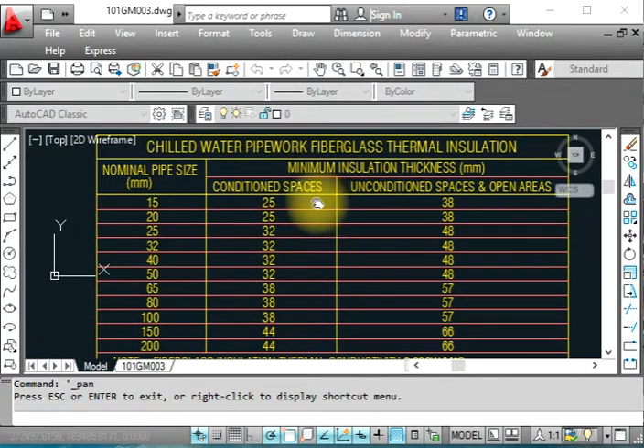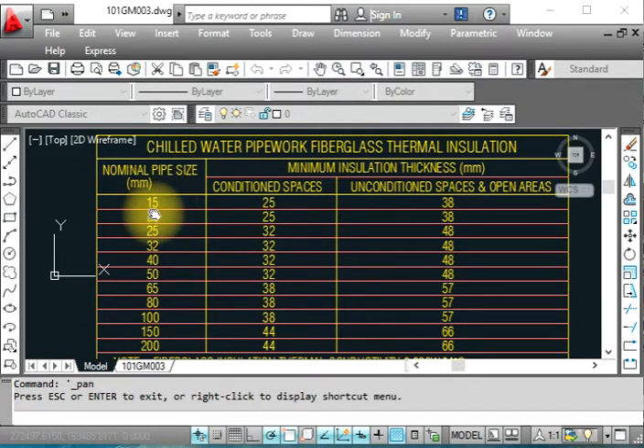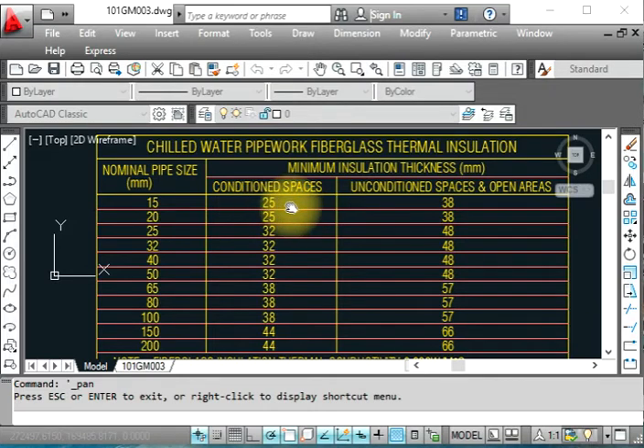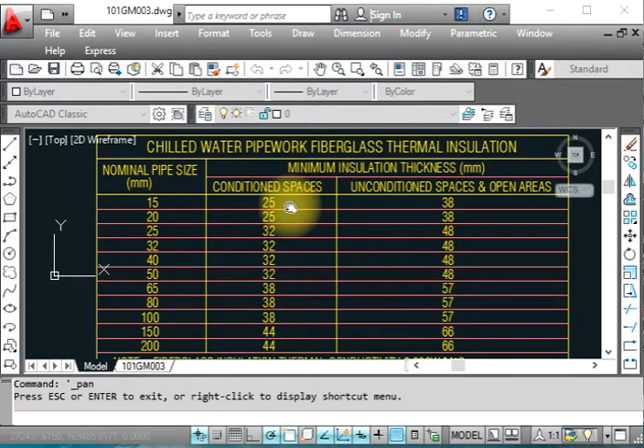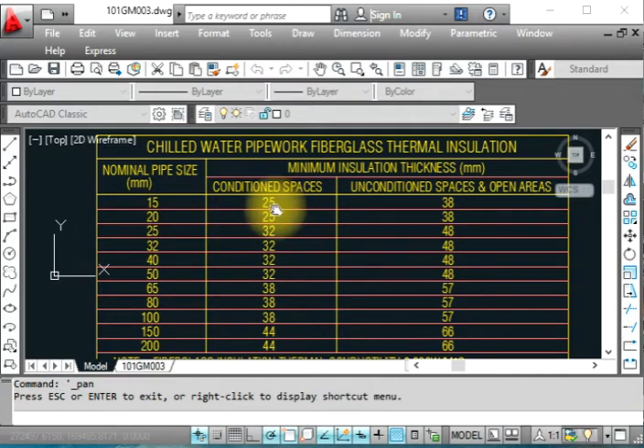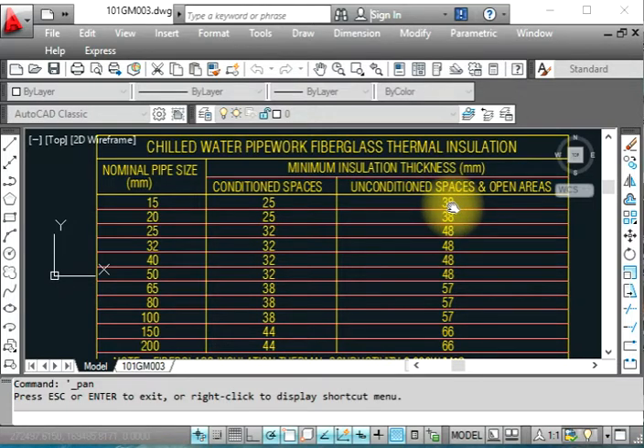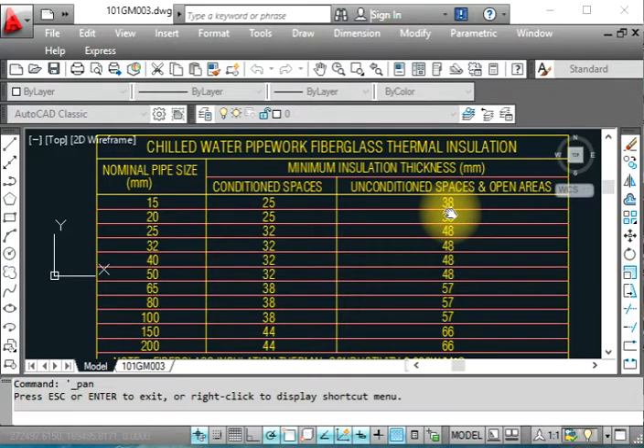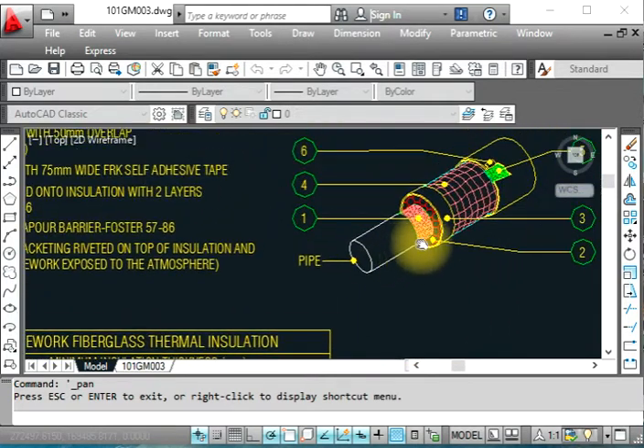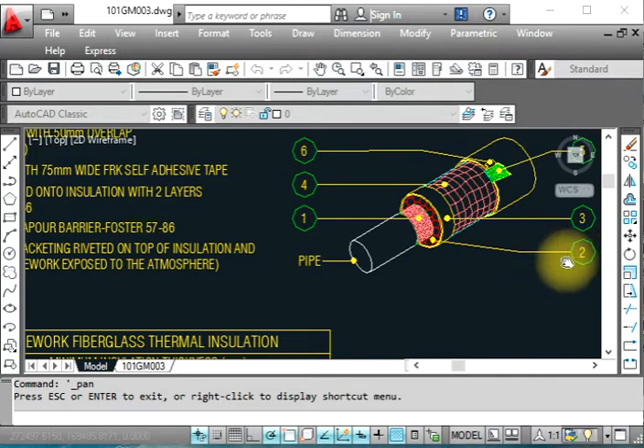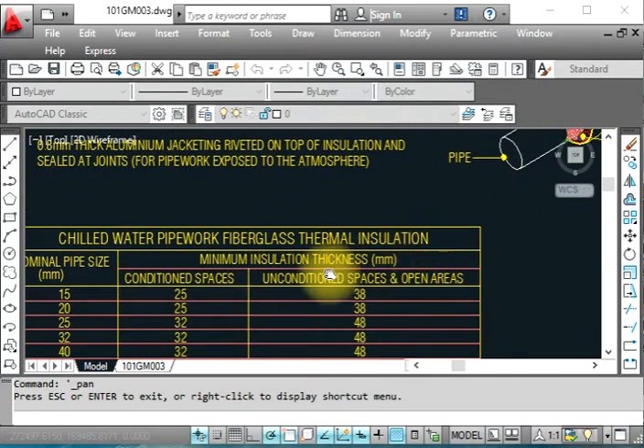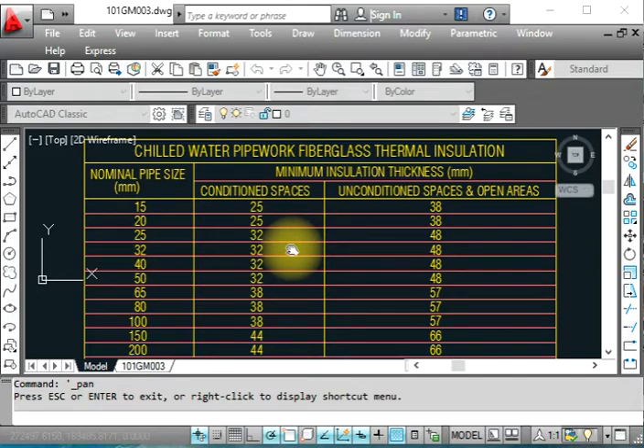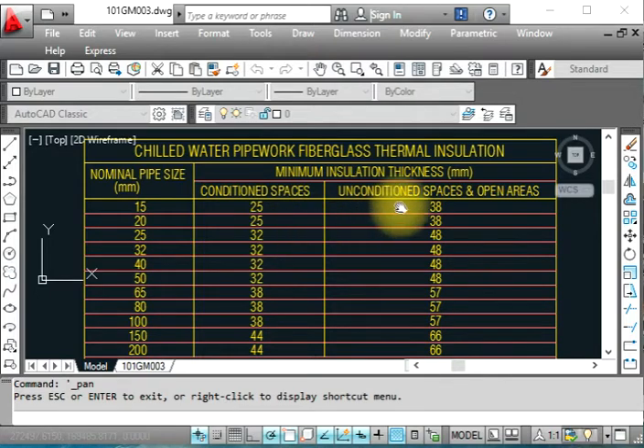This table shows chilled water pipe fiberglass thermal insulation. For nominal pipe sizes, if you have 15 mm pipe in conditioned space, we use 25 mm insulation thickness. Conditioned space means inside the roof, in office areas, rooms, and parking areas. If it's exposed area under the sun, we have to provide 38 mm fiberglass insulation thickness. Number two refers to the fiberglass insulation layer.